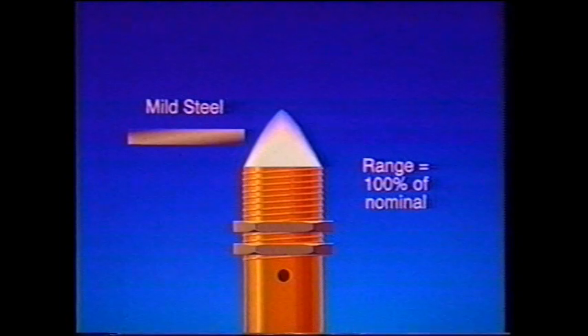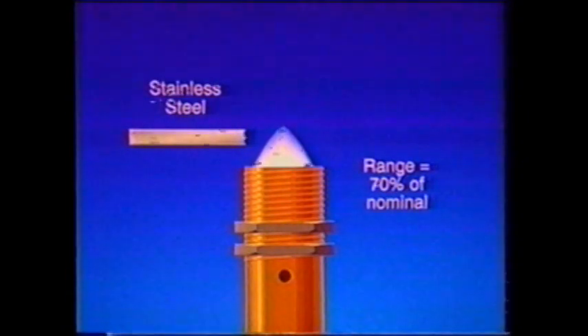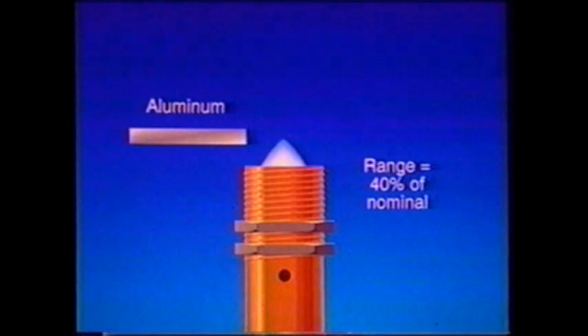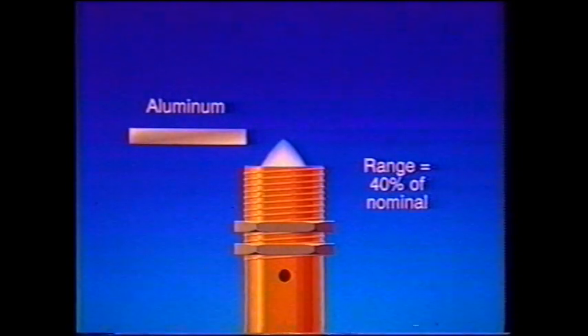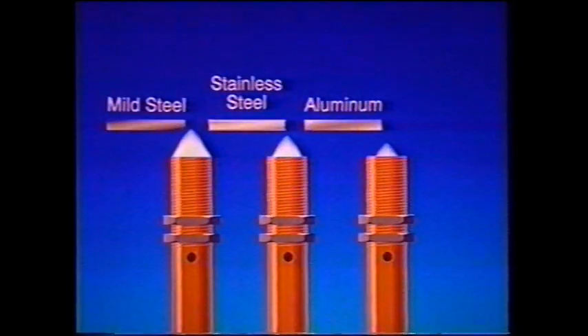The turn-on, turn-off graphs we saw earlier were based on a mild steel target. When the target is not steel, the graphs for the switch will be different. With a stainless steel target, the maximum sensing range will only be about 70% of the nominal range. And with an aluminum target, the actual sensing range will be only about 40% of the nominal range. Remember to correct for the material, and then have the switch operate at 50% of that range.